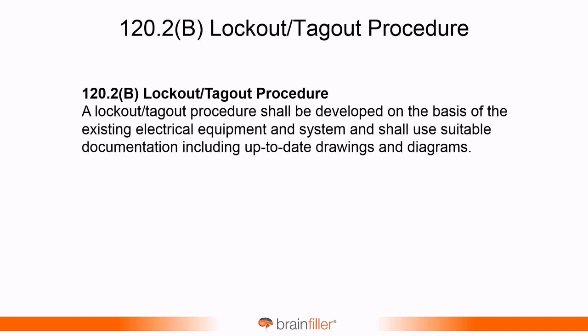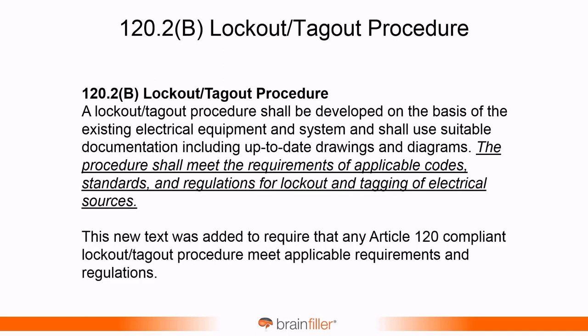There were a few revisions made here. 120.2(B), the lockout, tagout procedure, this text right here has an addition to it now. So the procedure shall be developed on the basis of the existing electrical equipment and system and shall use suitable documentation, including up-to-date drawings and diagrams. I'm going to talk about that one in a moment. However, there's an addition. The procedure shall meet the requirements of applicable codes, standards, and regulations for lockout and tagging of electrical sources. So this was added to make sure that any lockout tagout procedure meets applicable requirements and regulations.